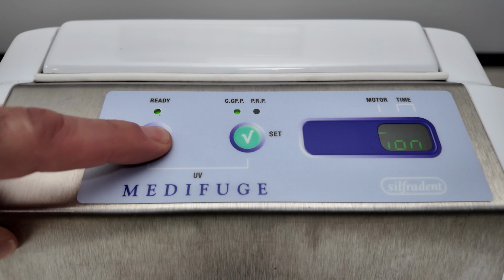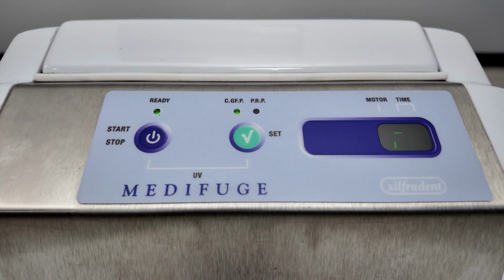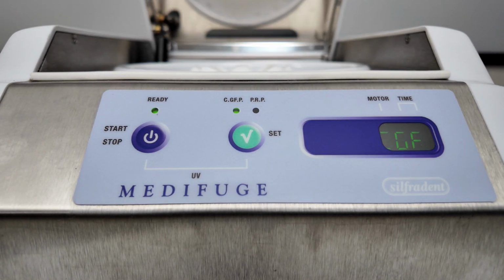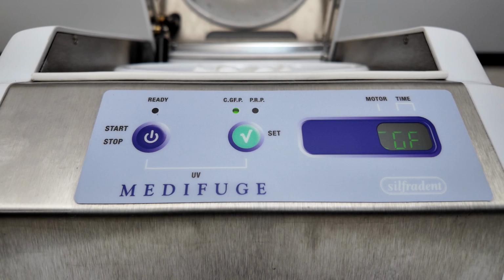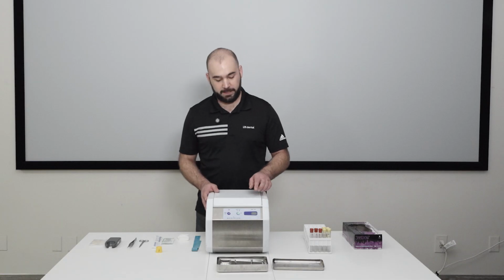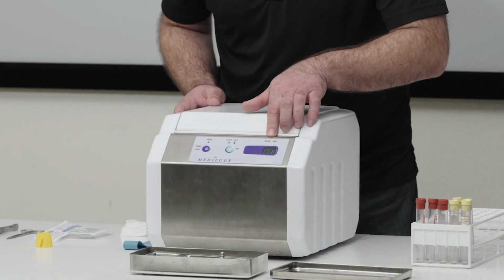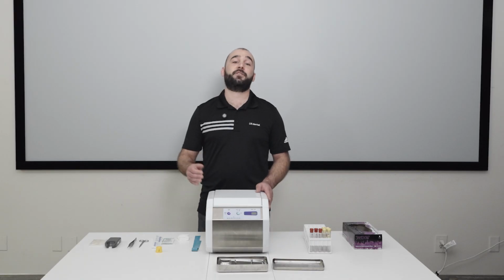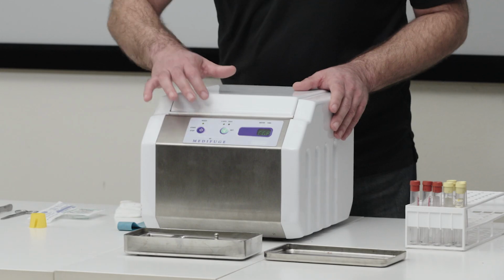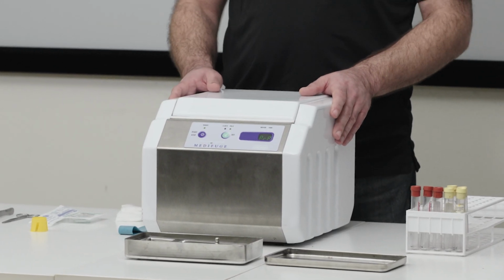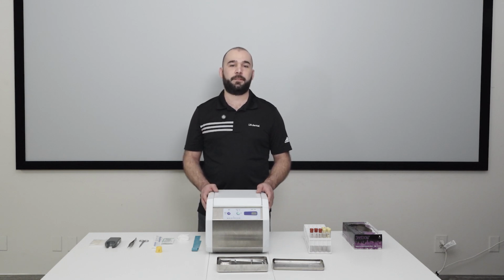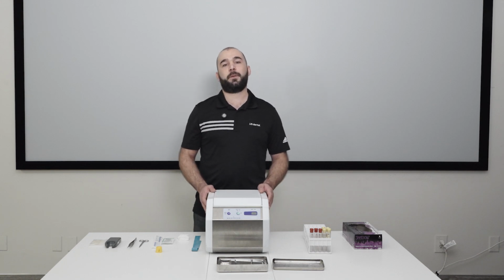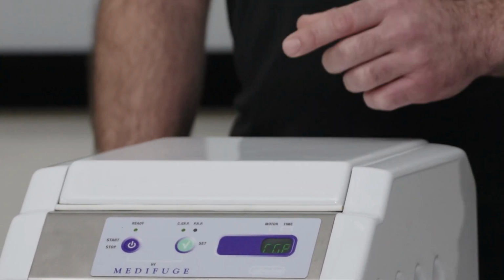If you ever need to stop the spinning, just press the same button again. Notice the machine will gradually slow down, and once the spinning is completely finished, the lid will automatically open. Never try to force the lid open. Every time you turn on the power, you'll see that the device always displays CGF first, which refers to concentrated growth factors. If you press the mode button, it switches to PRP, or platelet-rich plasma. While PRP is still used for certain orthopedic procedures, in dentistry and general implantology, you will rarely need it. Just set it to CGF for the best results.